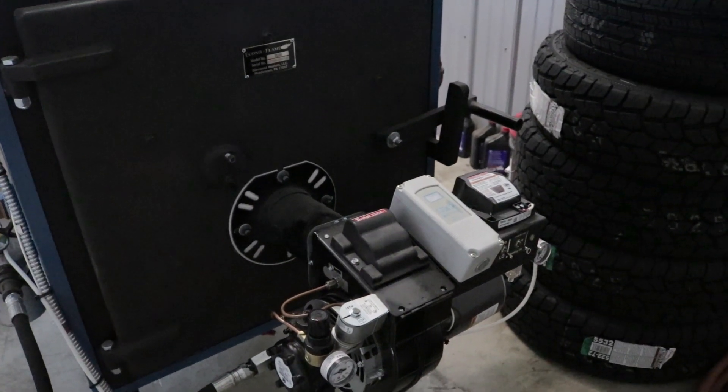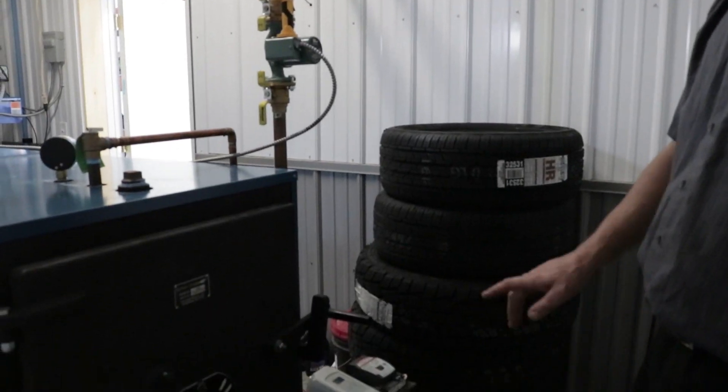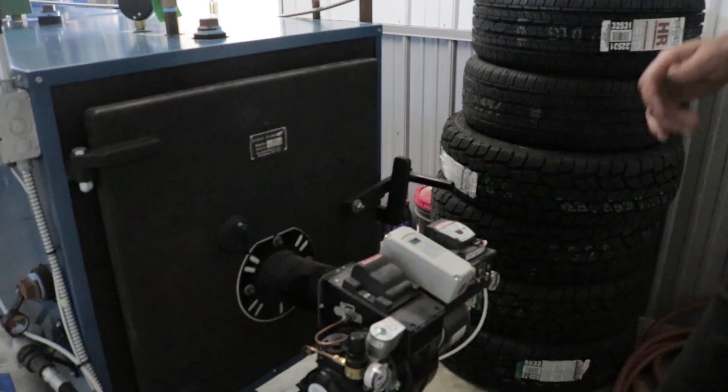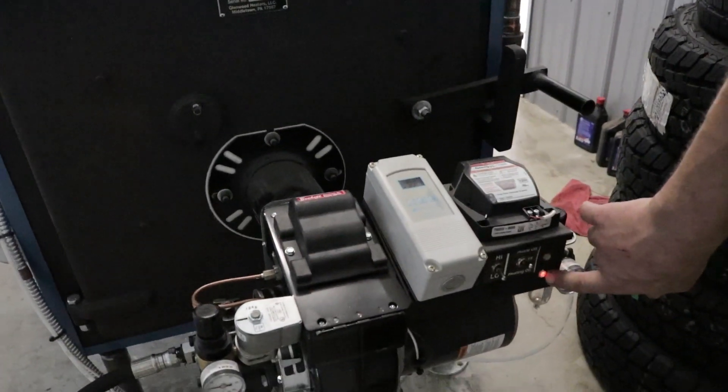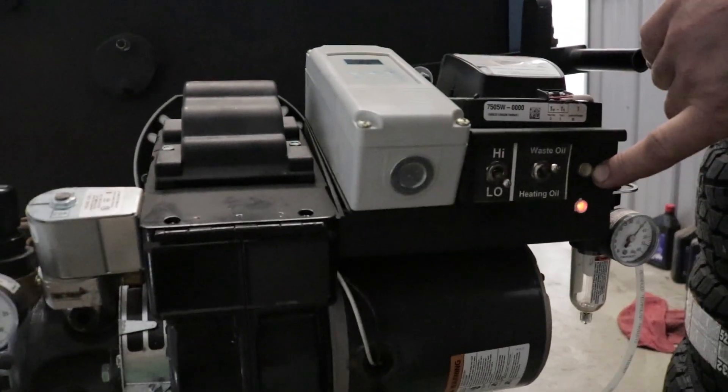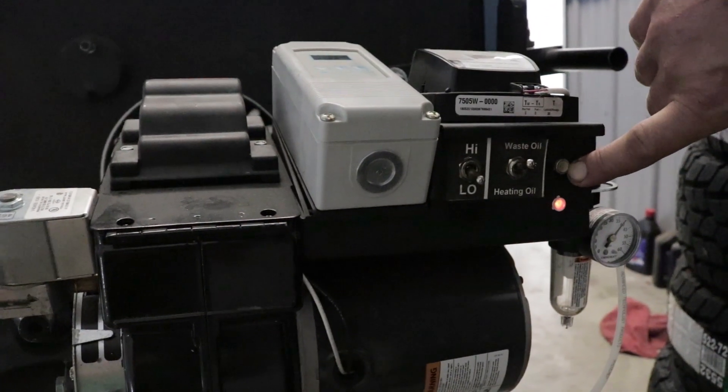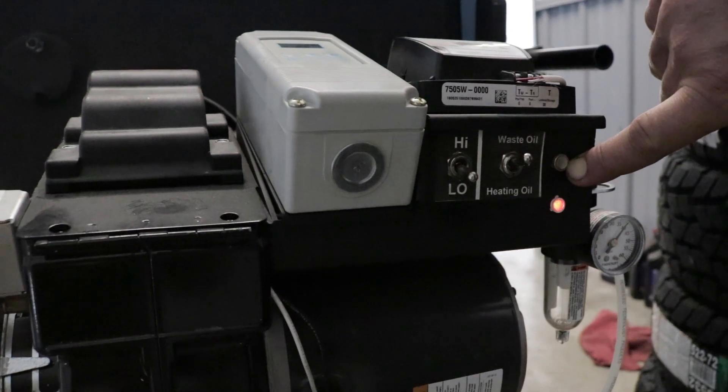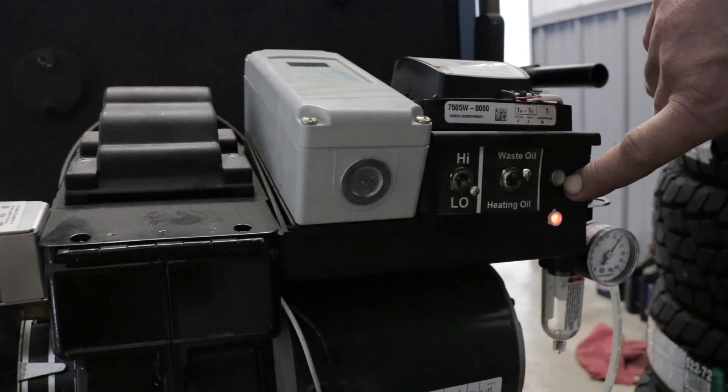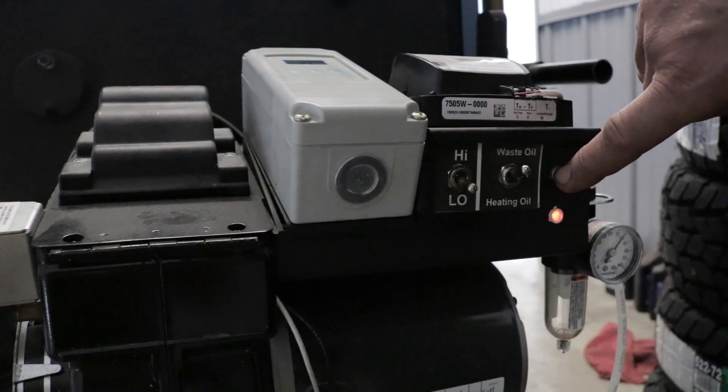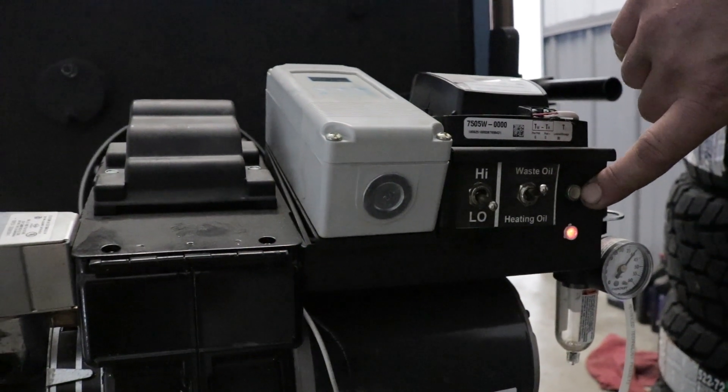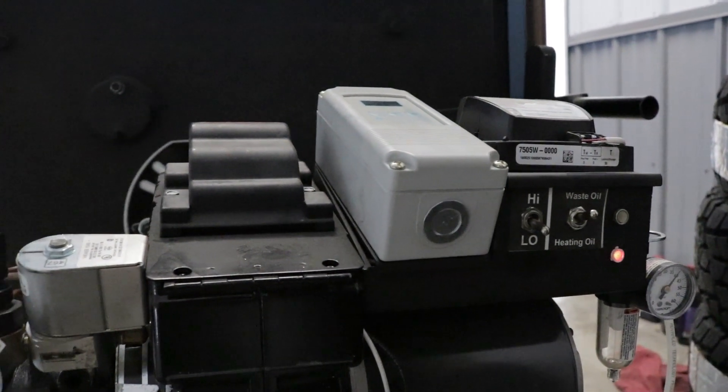There are indicator lights on the burner that tell you when what is functioning. The red light tells you the preheaters are functioning. The green light will tell you that the burner is in run mode. It may not necessarily be running, but it will be in run mode. The times when the green light will be on when the burner is off is if the boiler is satisfied—it's not calling for heat.